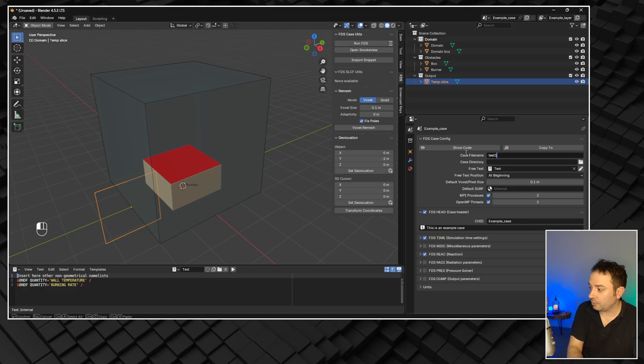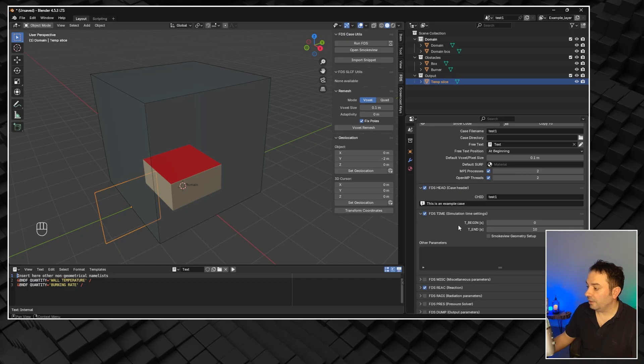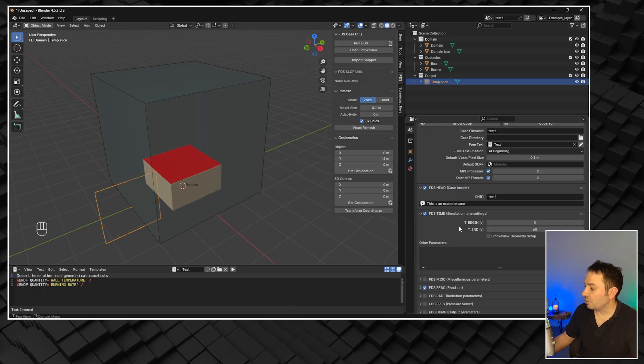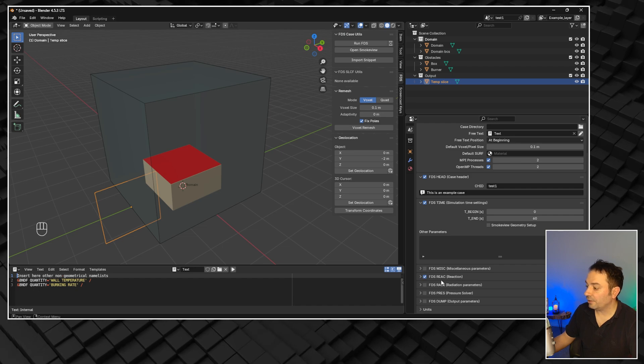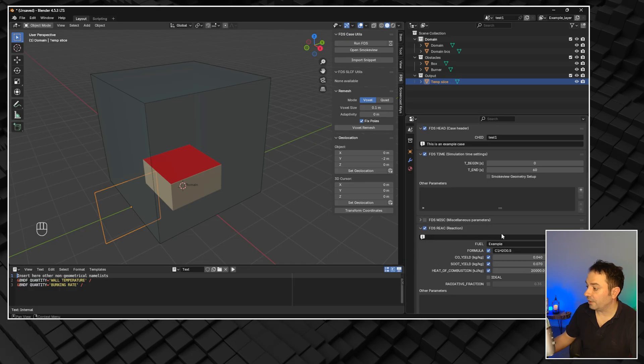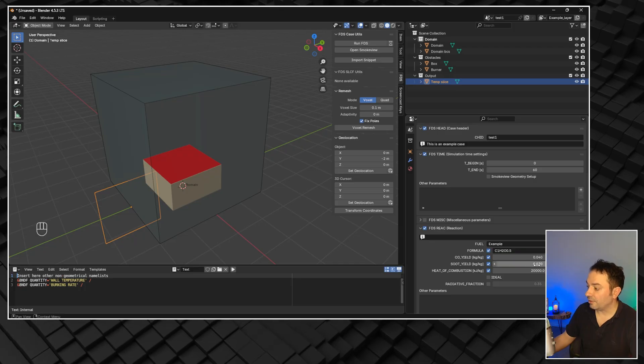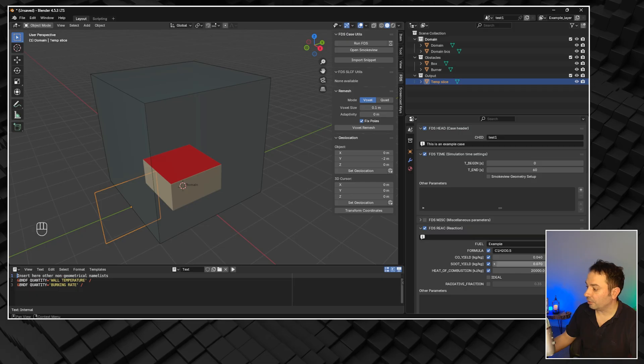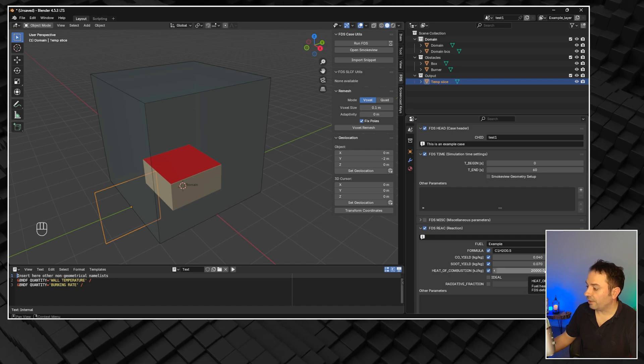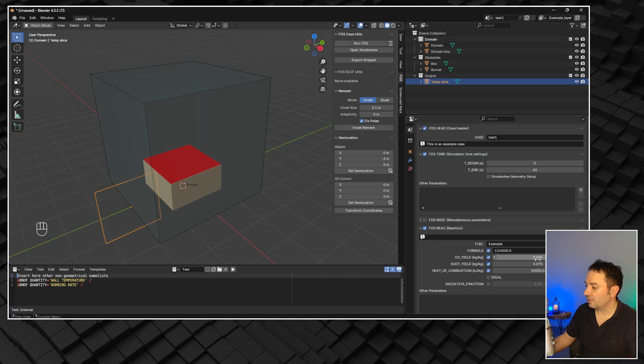You have the possibility to modify the duration of the simulation — currently set to 10 seconds. Let's change it to 60 seconds. Here you can also see the reaction defined for this project: the material that is burning, CO yield (the amount of CO released when combustion is not fully happening due to insufficient oxygen), soot yield, and heat of combustion. You can check handbooks and the latest papers for your specific material and modify these three parameters accordingly.